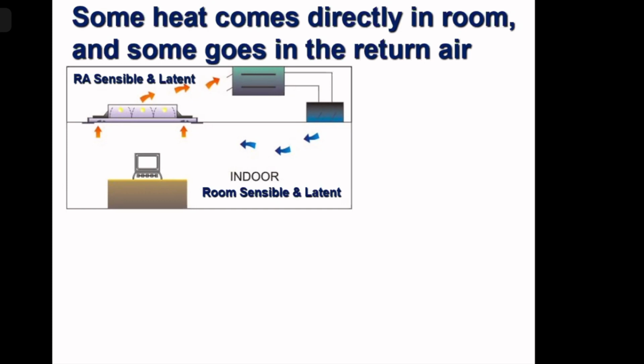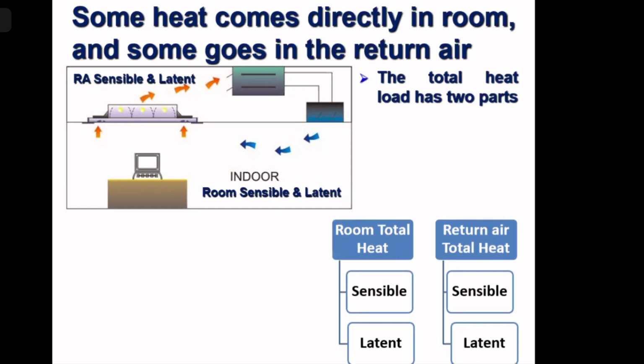So that 24 degrees centigrade air, which is shown by the red air, goes up above the false ceiling, which is the return air space, and it is taken out of the room. So heat comes in two ways. Now, next. Okay. So heat comes in two parts. One directly in the room, which we call room total heat. One in the return air space, which is the return air total heat.